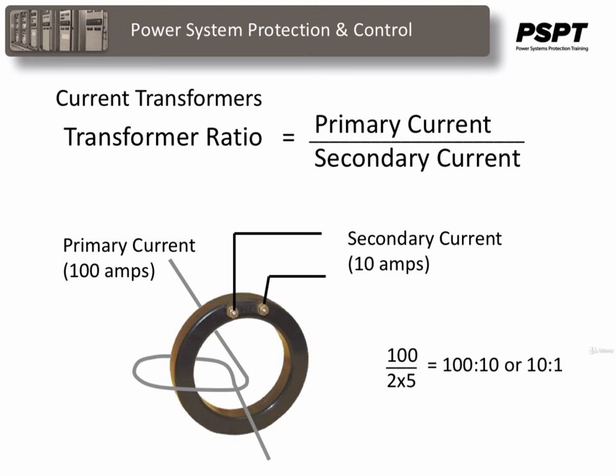This is sometimes used if the primary current is too low for a meter to be able to read. You simply loop the primary conductor through another time, and you could actually loop it through a couple of times if you want, and that would increase the amount of current flowing in the primary that the CT would see.